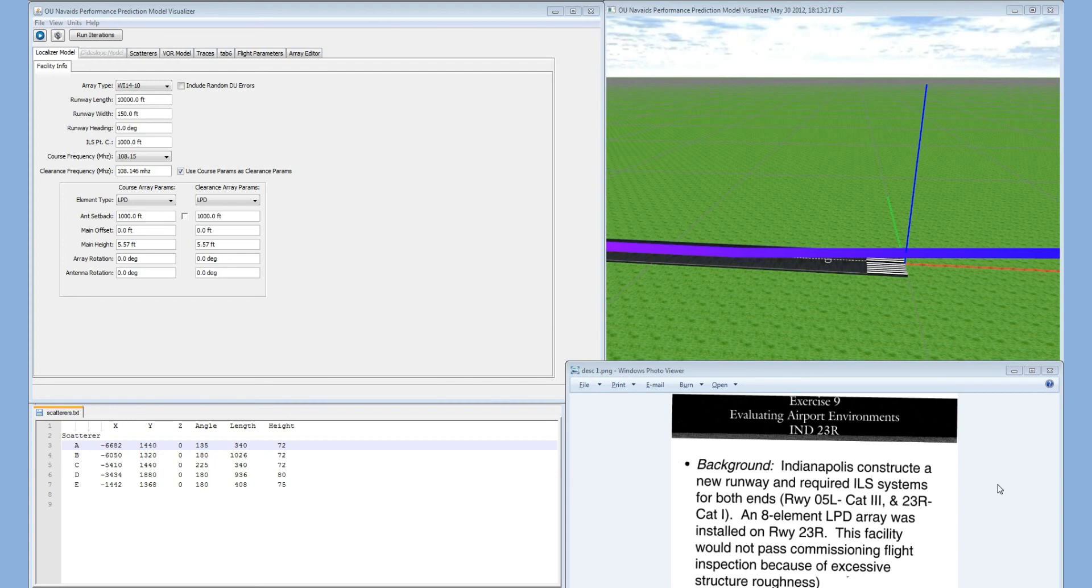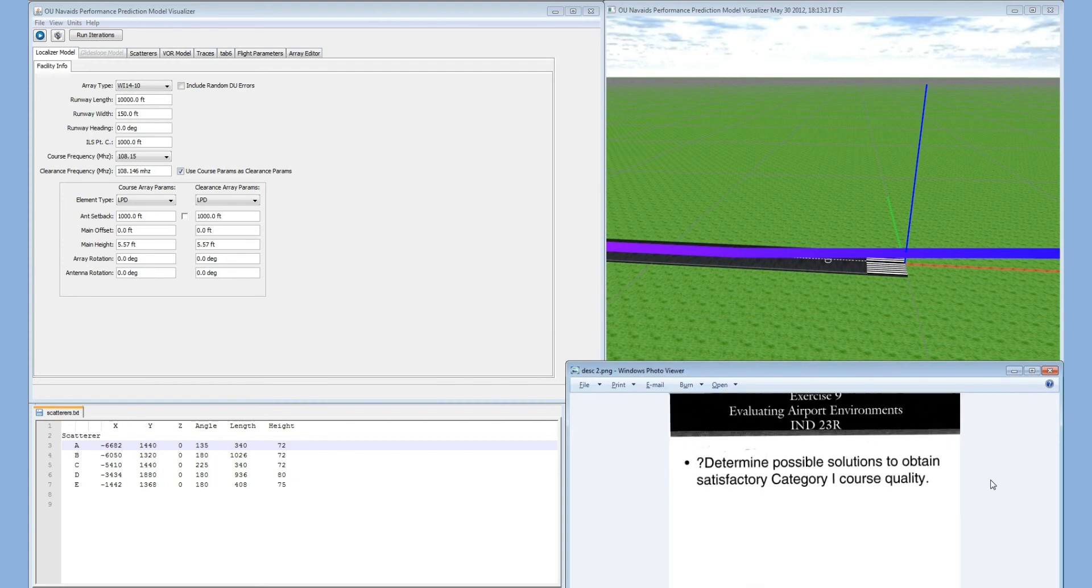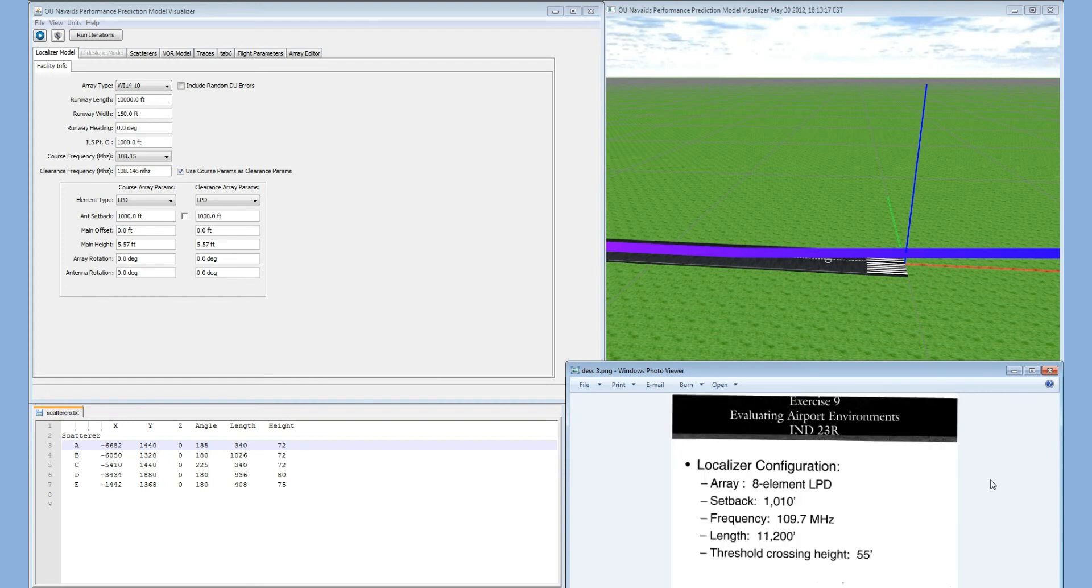An eight element LPD array was installed on runway 23R. This facility would not pass commissioning flight inspection because of excessive structure roughness. We are going to recreate this model and verify that the runway is indeed out of tolerance, then change the simulation to make the model within tolerance. We would like to determine the possible solutions to obtain satisfactory Category 1 course quality.